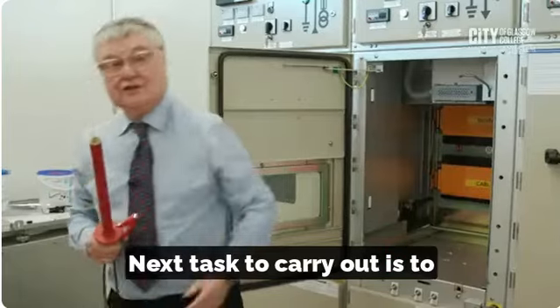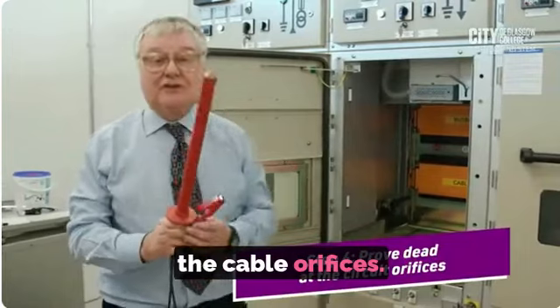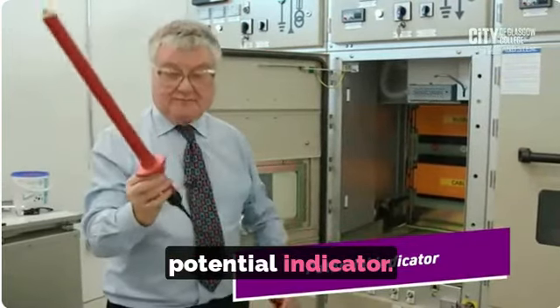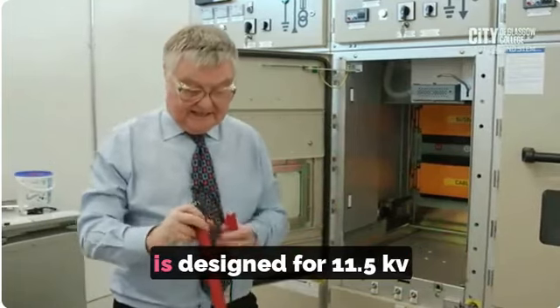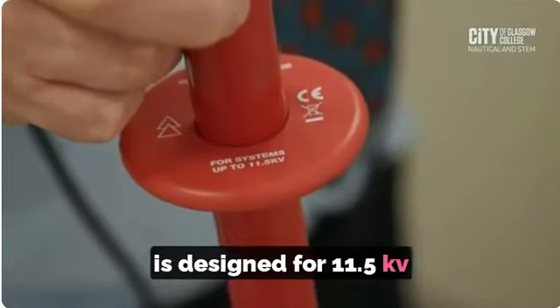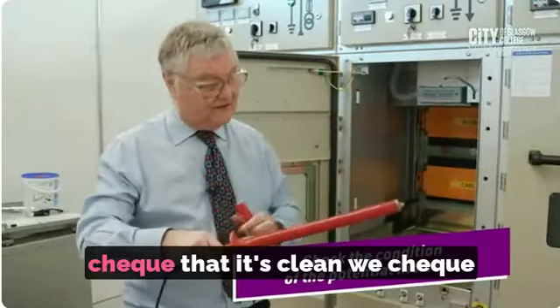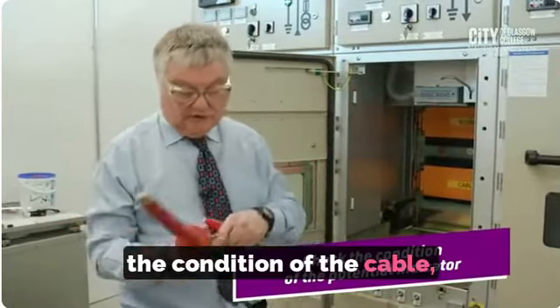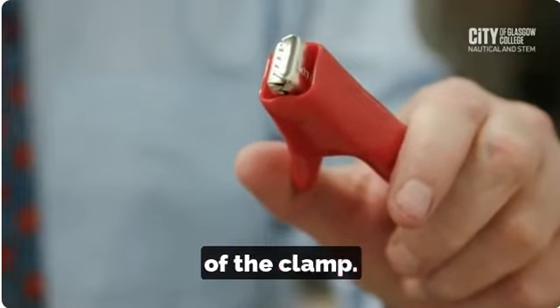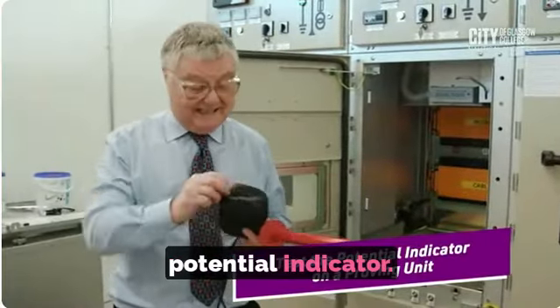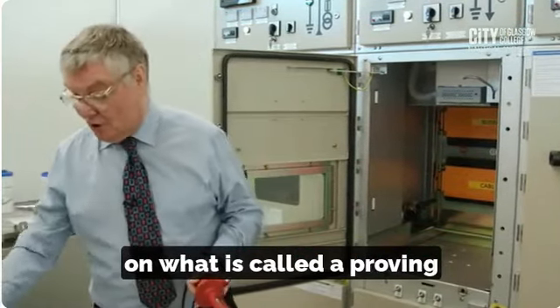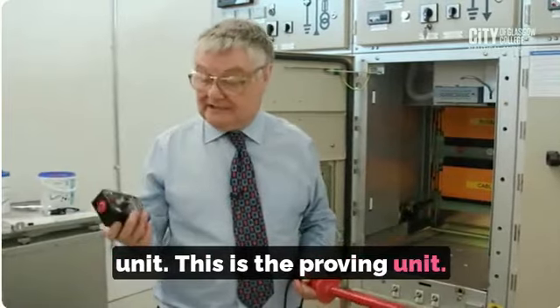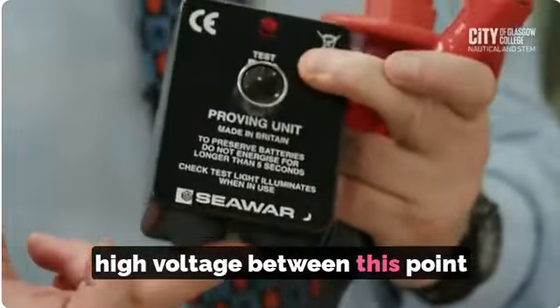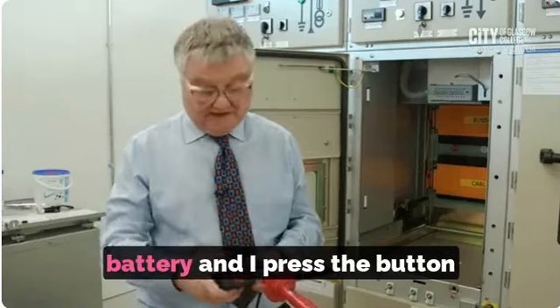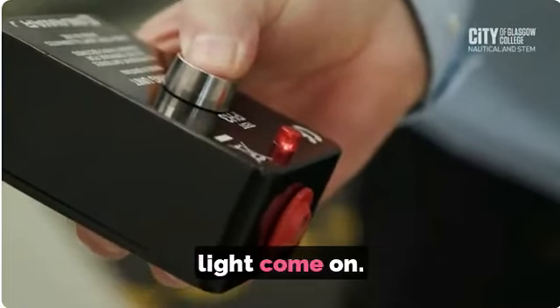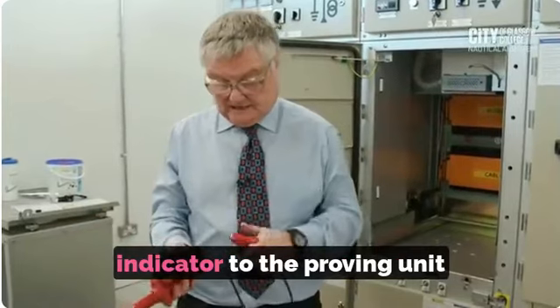Next task to carry out is to prove the circuit dead at the cable orifices. To do that, we use what's called a potential indicator. This potential indicator is designed for 11.5 kV, and we check its condition, check that it's clean, we check the condition of the cable, we check the condition of the clamp. We then test the actual potential indicator. We test the potential indicator on what is called a proving unit. This is the proving unit. What it does is it produces a high voltage between this point and this point from a 9-volt battery. When I press the button, you should see the red light come on.